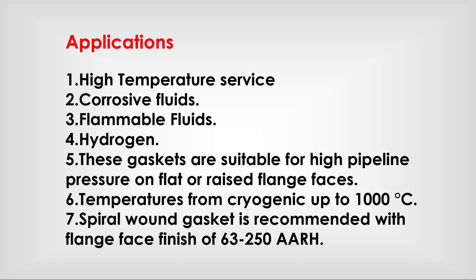Applications include high temperature service, corrosive fluids, flammable fluids, and hydrogen. These gaskets are suitable for high pipeline pressure on flat or raised face flanges, with temperatures from cryogenic up to 1000°C. Spiral wound gaskets are recommended with a flange face finish of 125 to 250 AARH.